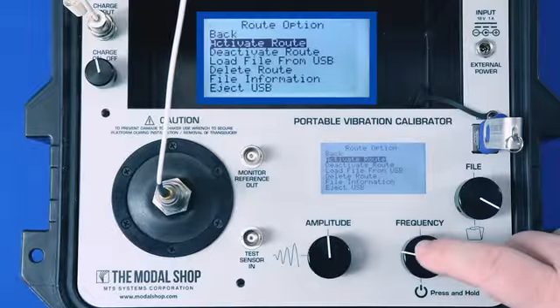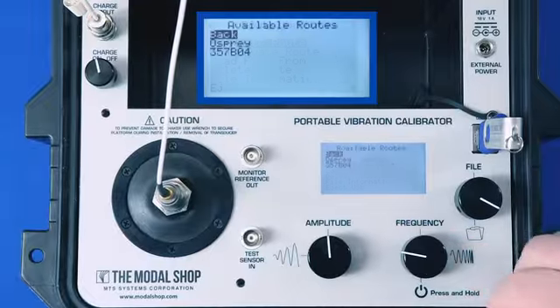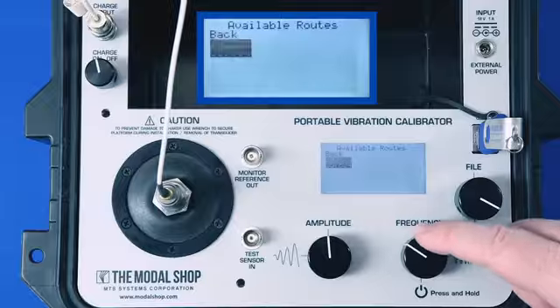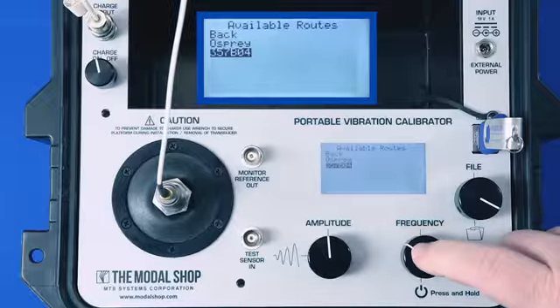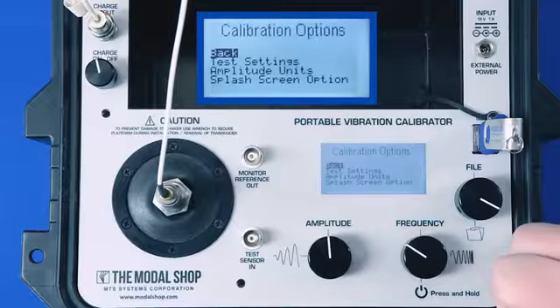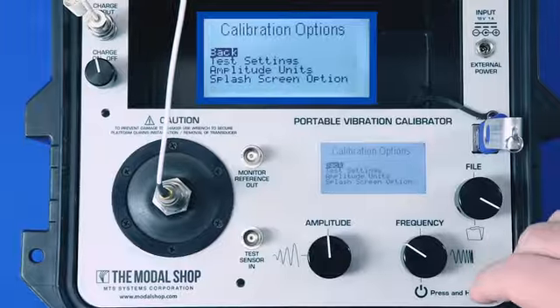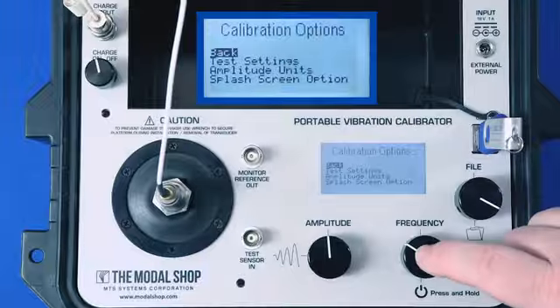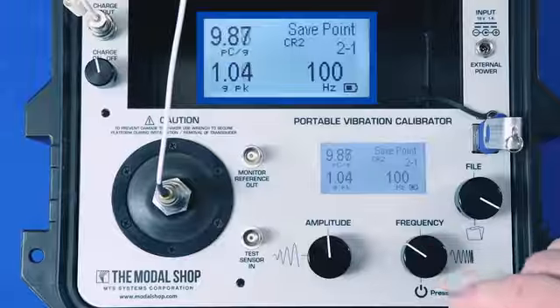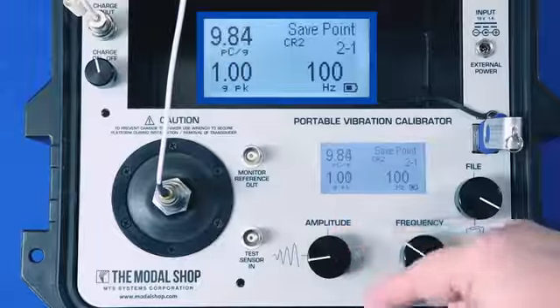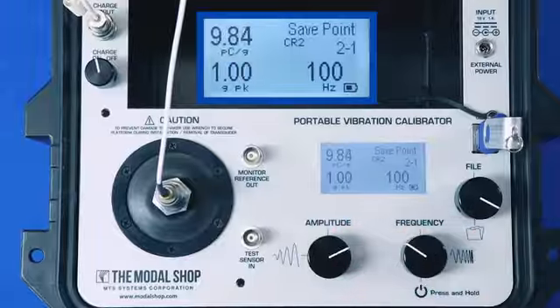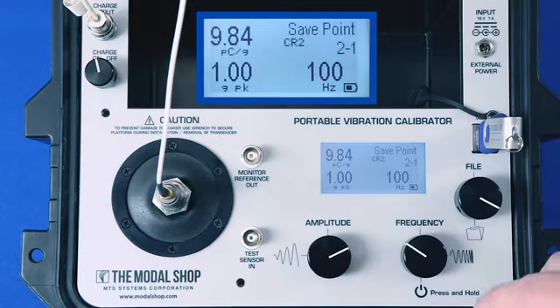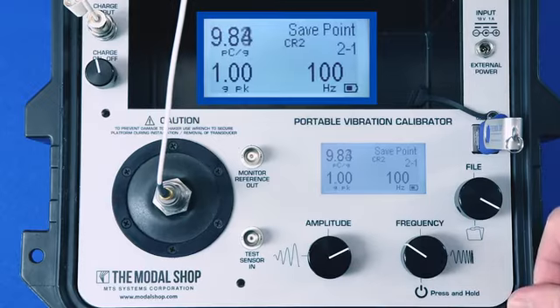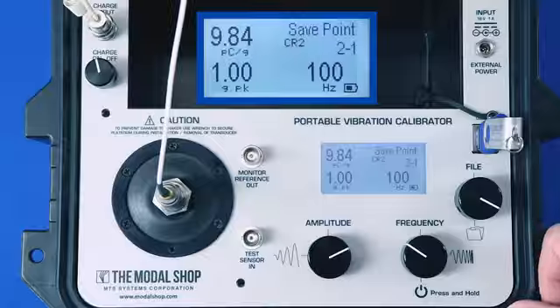So that joins my list of tests that are stored in the memory of the calibrator, and I can activate it by clicking Activate and choosing the appropriate test. Now I'm locked in to that step sine test. I can't use the shaker in manual mode anymore. If I turn the amplitude dial, nothing happens. I'm locked into my pre-programmed test, which is going to start at 100 Hertz.